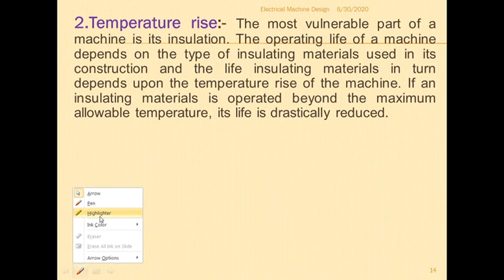The operating life of a machine depends upon the type of insulating materials used for its construction. The operating life of the machine, how long the machine will be running, again depends upon the type of insulating materials which you are providing. So which type of insulating material you are using, and what is the temperature limit of that particular insulating material. We have to calculate what is the maximum allowable temperature that particular machine may take when it is running continuously. Correct. So based on that, we have to use certain types of insulating materials for that particular machine.